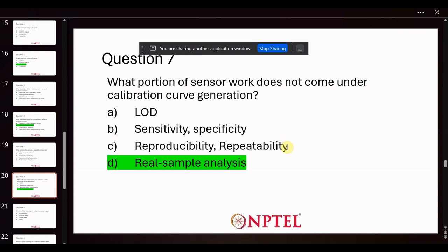That is, what a specific value of voltage corresponds to. We can take the example of a glucose sensor. What specific voltage corresponds to what specific amount of glucose is what you have to determine. You take normal samples with known values, use your sensor with these different values, and then get the calibration curve. It is expected that the calibration curve is straight in nature. Where it is straight, your sensor is really good. Obviously you cannot get a perfectly straight curve, but your aim has to be as straight as possible. The origin might not be zero.